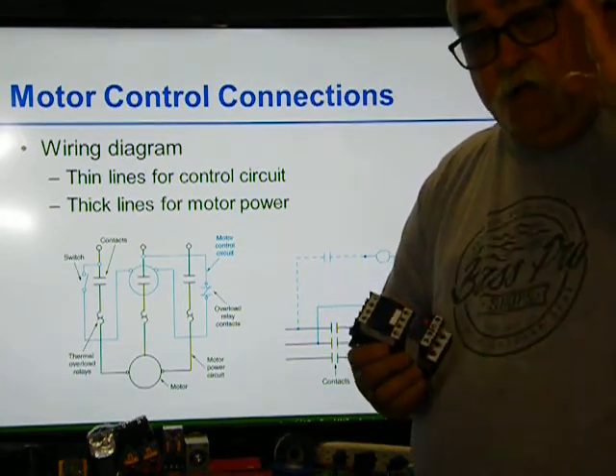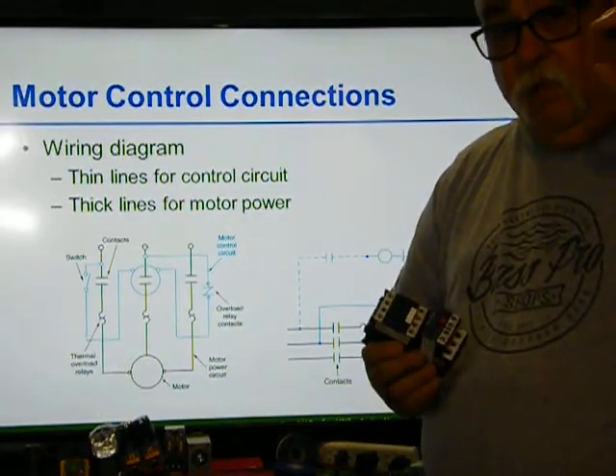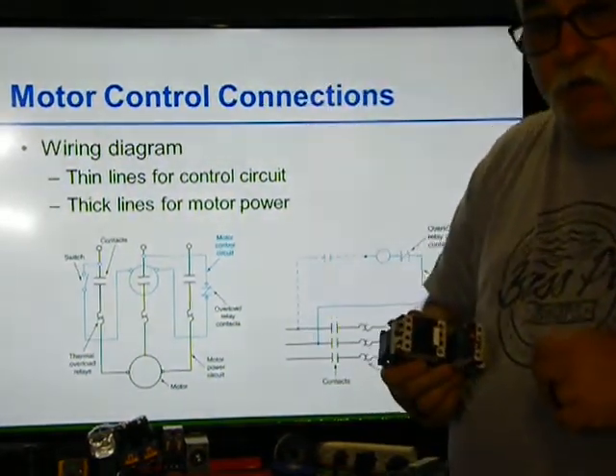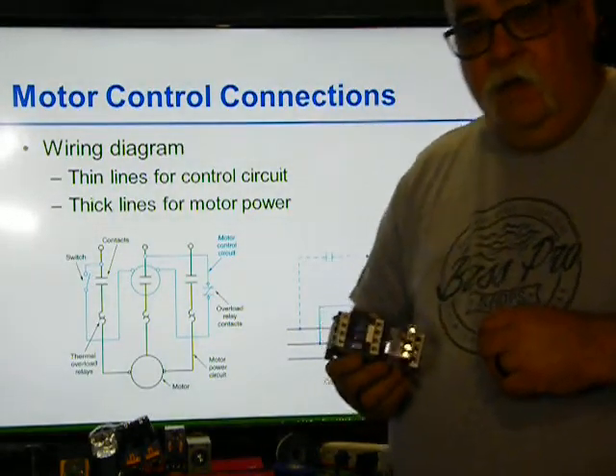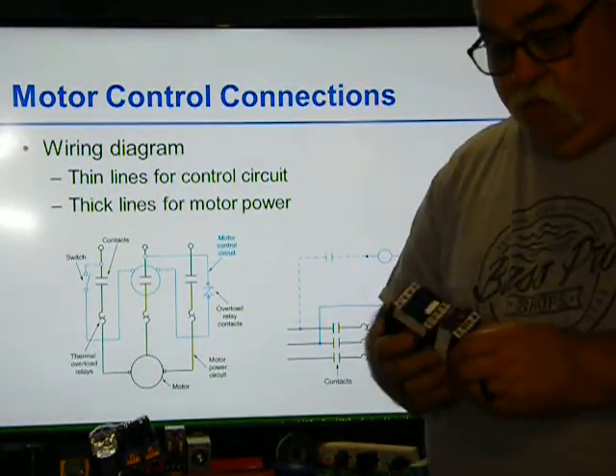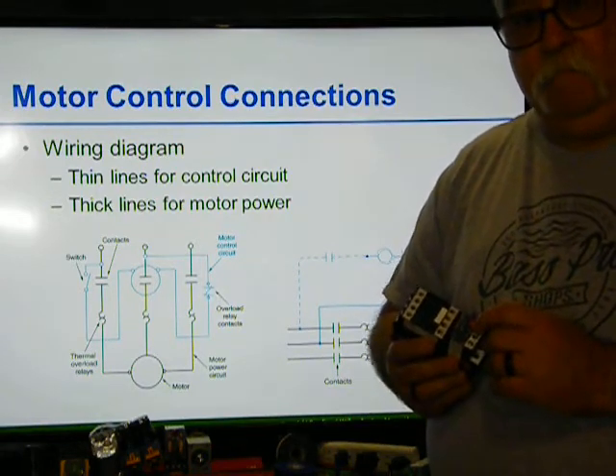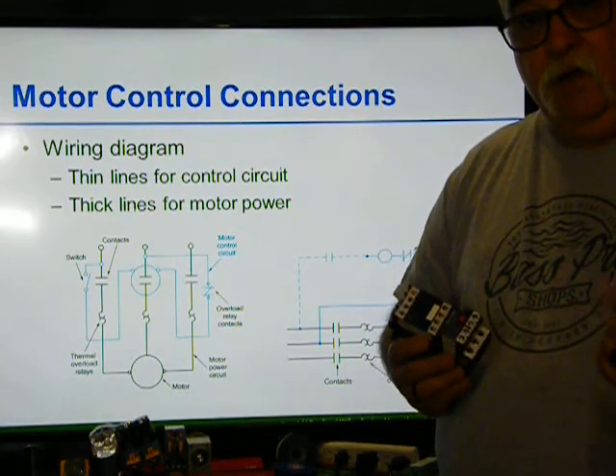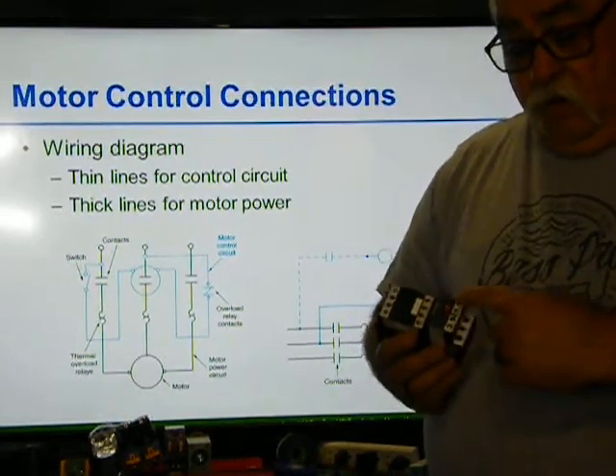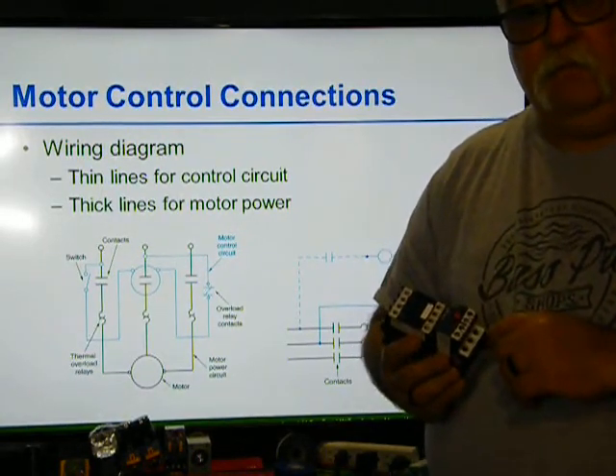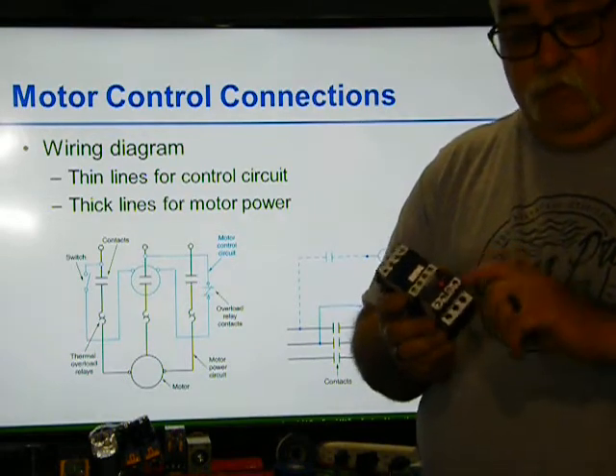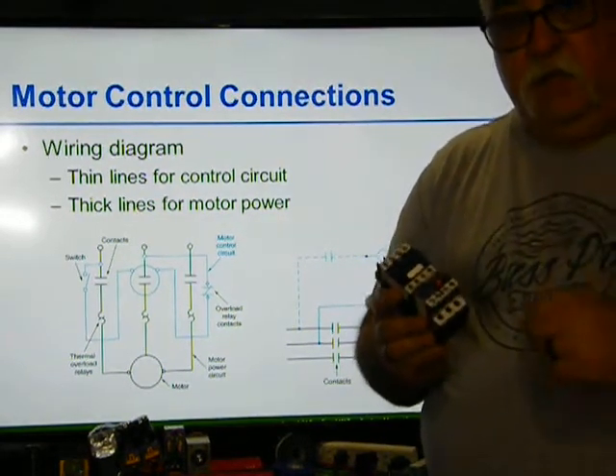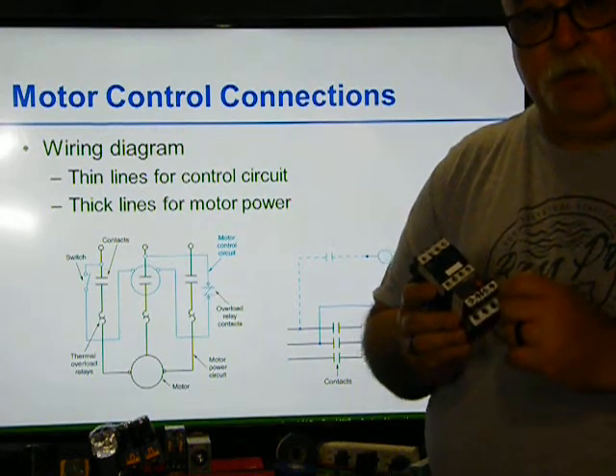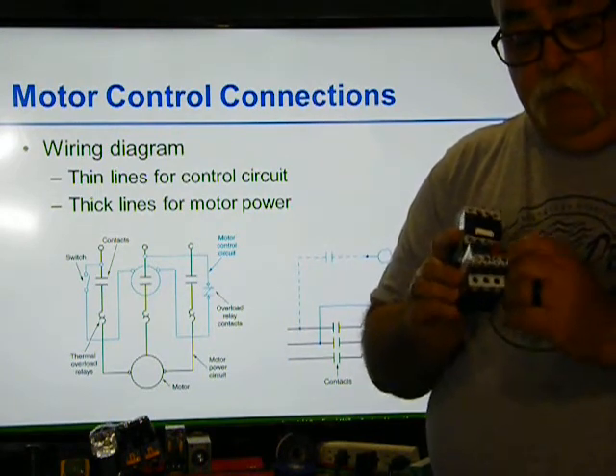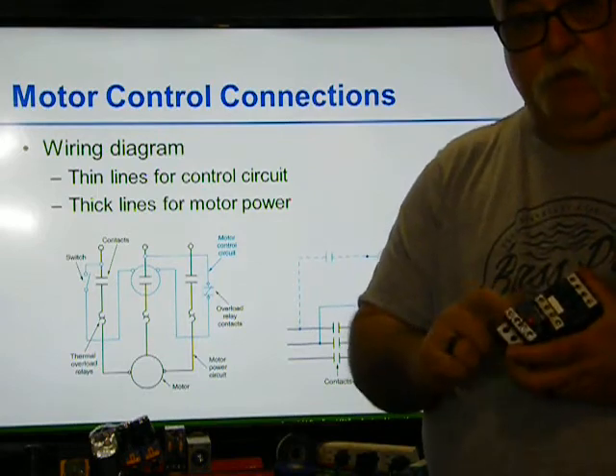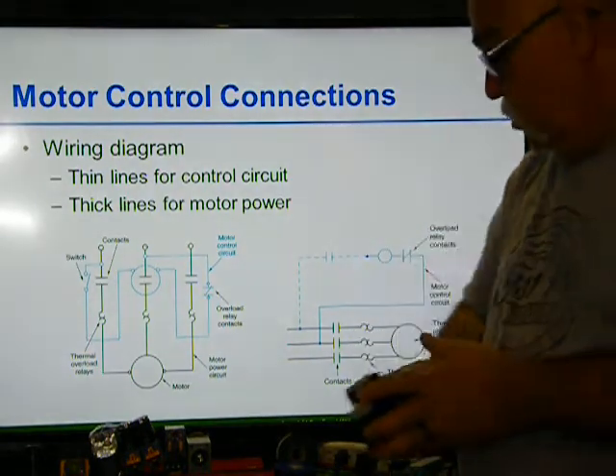As that heat gets up, if there's a problem, if the motor's running too hard because you haven't oiled the bearings in 6 months to a year, you haven't changed the belt, and the belt's starting to tighten up, or you got the belt too tight, and the motor starts to get hot. Well, that heat goes on the wire, comes to here, this trips out. It's got this little red button. If you're hitting the stop-start and it doesn't come on, more likely this tripped out. What you have to do is come over here, hit that red button, push it down. Now you can reset the overloads.